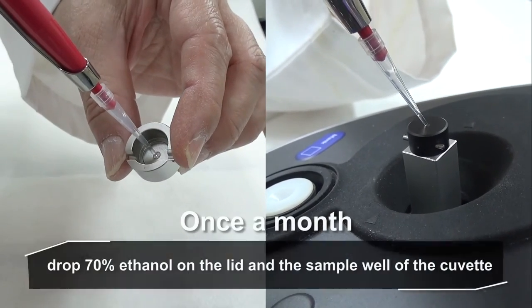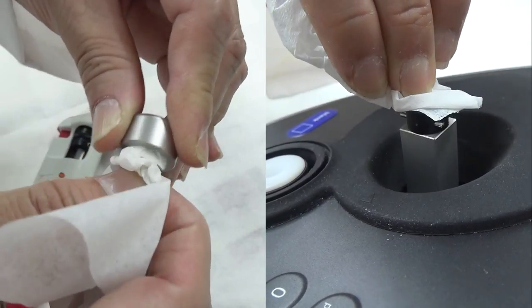21. Once a month, drop 70% ethanol on the lid and the sample well of the cuvette and wipe clean with a Kim wipes tissue.